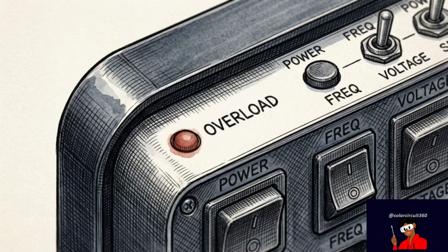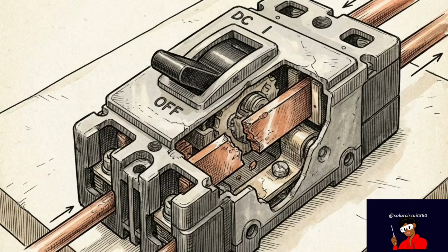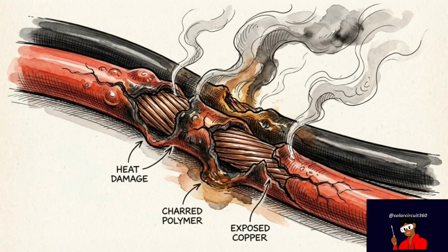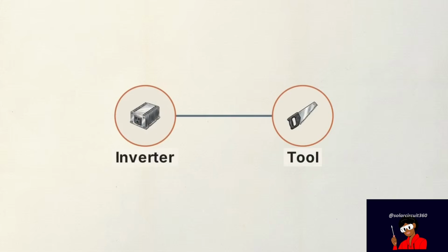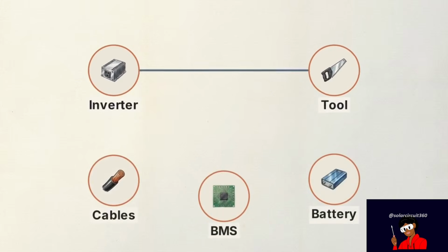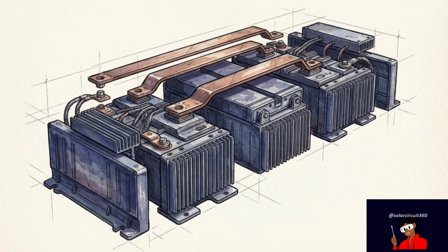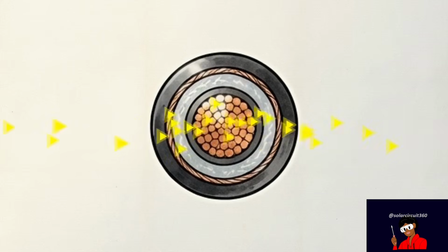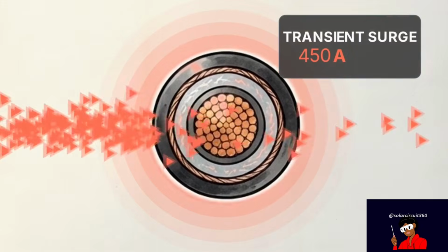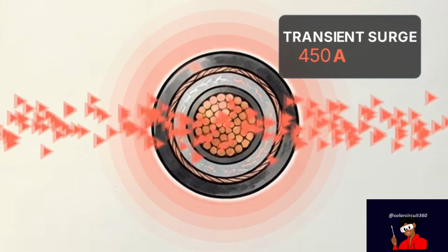Inverters flash overload faults, battery connections trip, and in worst cases, wiring melts. Properly powering a workshop requires treating the inverter and tool as a full system engineering problem, rather than a simple AC matching exercise. The actual culprits behind these failures are hidden on the direct current side of your system, specifically transient power surges and the massive, invisible DC current draw they create.